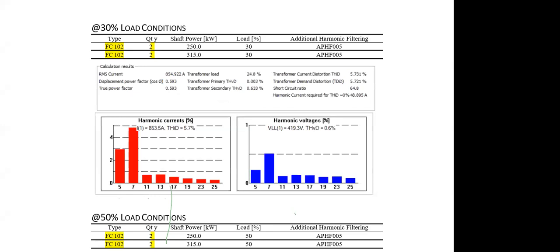Now here you see how it is achieved. When we talk about total harmonic distortion, it means the total harmonic distortion is for current as well as voltage. While doing this, we came to know there is a possibility that if I take some fixed speed loads into the main load of that 2500 kVA transformer, say I have 10 motors, 5 fixed speed and 5 variable, I take the advantage of fixed speed because there is no harmonic distortion. So I add this. In that case, my current harmonic is achieved, but voltage harmonic is not achieved. That's why this total harmonic distortion term comes in.